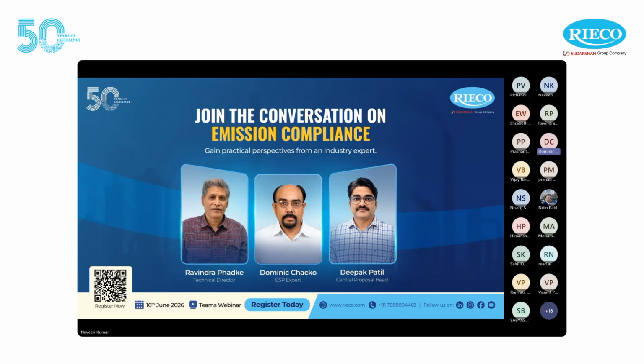So the ESP designer would have definitely taken that percentage of the moisture which is likely to be in the flue gas for that particular application while sizing and designing that ESP. But if you allow false air leakages through either the inlet duct or any other point, what happens is that atmospheric air is never that high in moisture as compared to the flue gas. So this addition of air will lower the moisture content of the flue gas in the ESP, and that leads to a higher resistivity of the flue gas and dust which is treated by the ESP.